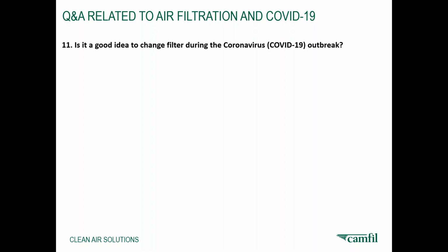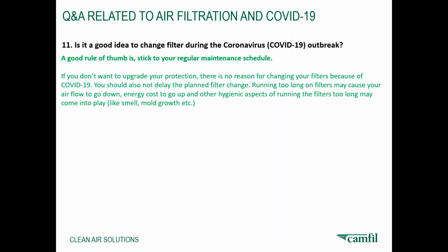Is it a good idea to change the filter during the COVID-19 outbreak? As I said earlier, it depends on your maintenance schedule - there's no need to panic and change the system. If the system has reached its pressure drop limit, definitely go for the change and upgrade the system. Because if you don't change it when the pressure drop is high, the energy cost will go up, and there are other hygienic aspects - smells can come, mold growth can occur. So follow your maintenance schedule.